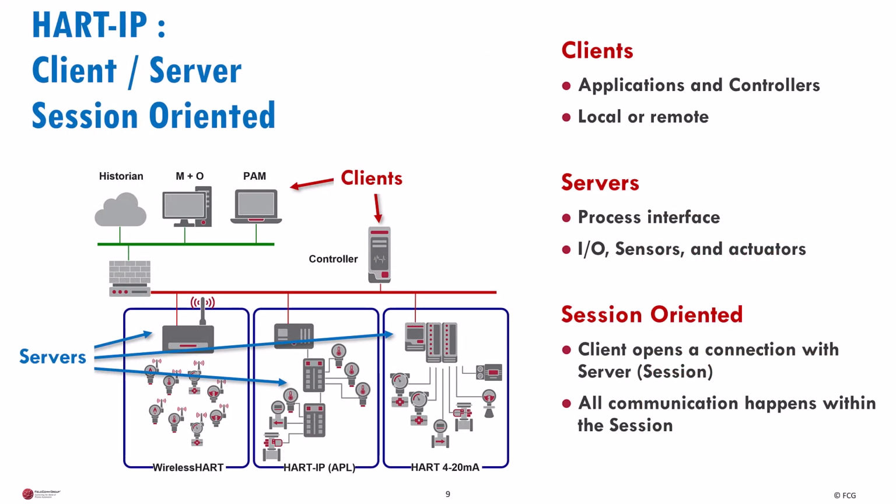HART-IP is a client-server architecture with session-oriented communications. Clients are typical applications you find in process automation, monitoring and optimization, process controllers, plant asset management, and what have you. The servers are essentially the process interface, and the servers are wireless HART gateways and remote I/O and HART-IP field devices. When we talk about session oriented, it means that the client has got to open a session and then all the communication occurs within that session.